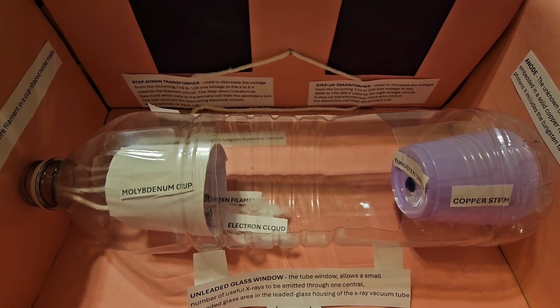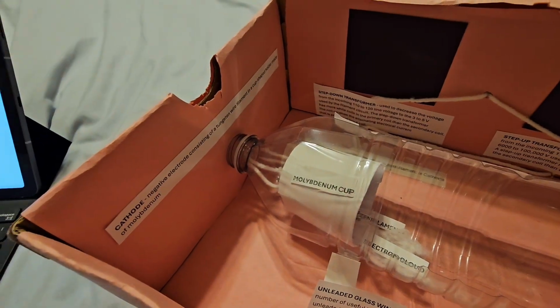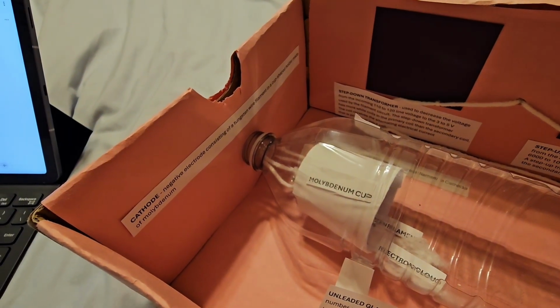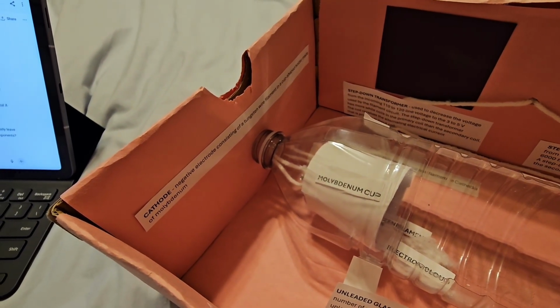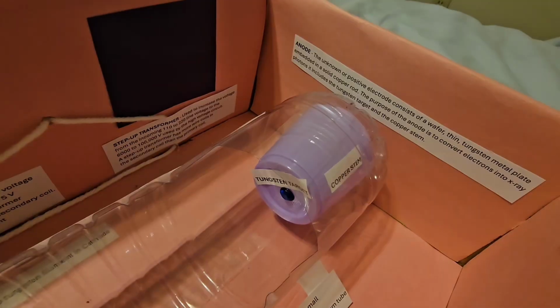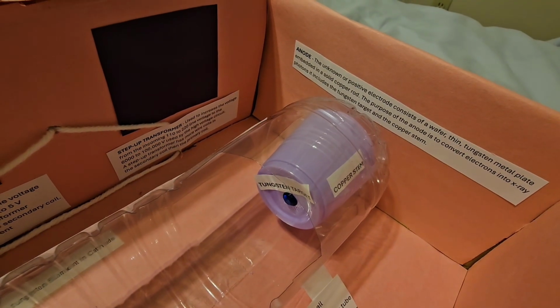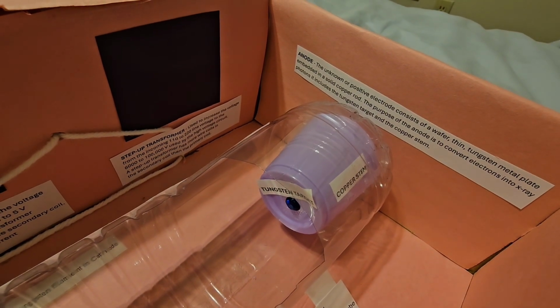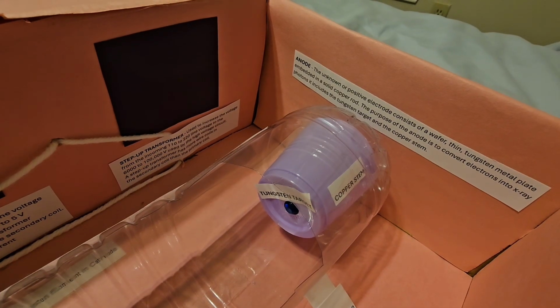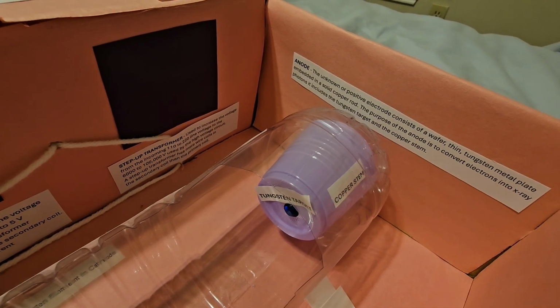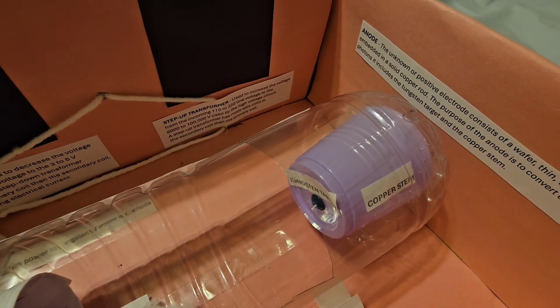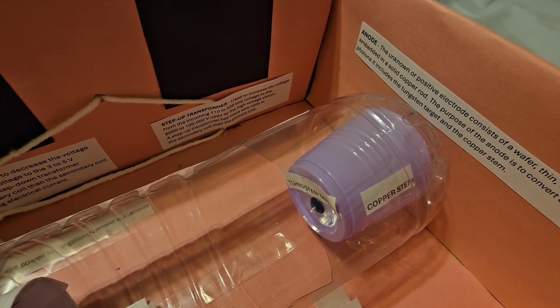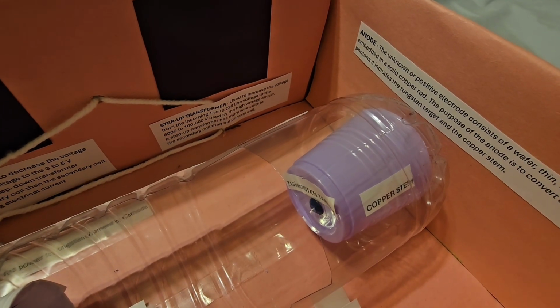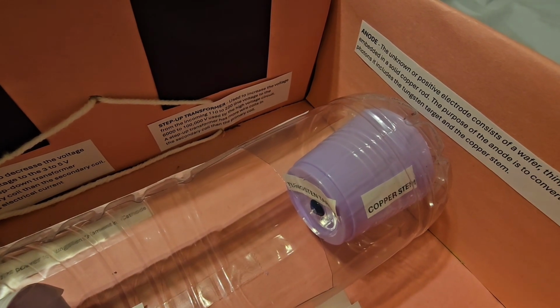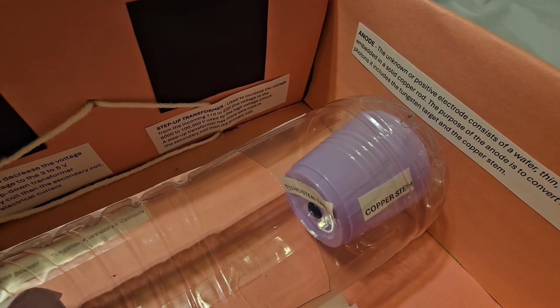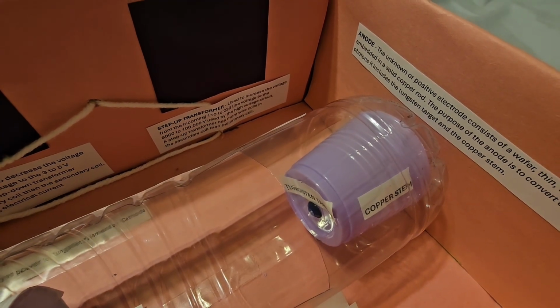Inside the glass housing are two main components: the cathode, which is the negative electrode. It supplies the electrons needed to generate X-rays. And the anode, which is the positive electrode. Its job is to convert those electrons into X-ray photons. The anode includes a tungsten target, which serves as a focal spot and converts electrons into X-ray photons, and a copper stem, which helps dissipate heat away from the tungsten target.